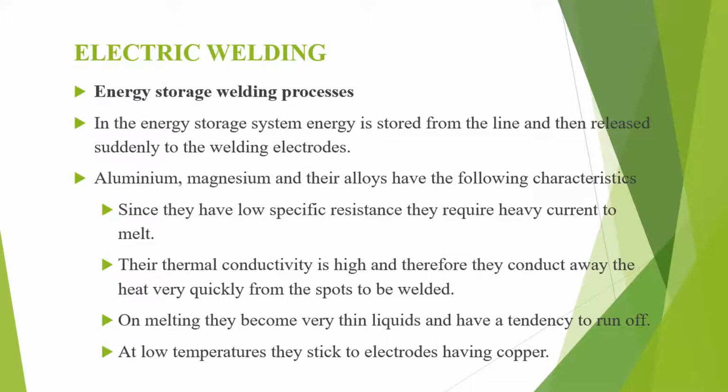Since they have low specific resistance, they require heavy current to melt. Their thermal conductivity is high and therefore they conduct away the heat very quickly from the spots to be welded. On melting, they become very thin liquids and have a tendency to run off. At low temperatures, they stick to the copper electrodes. To overcome the above problems, the welding should be done under high pressure in a very short time interval and use a very high volume of current.